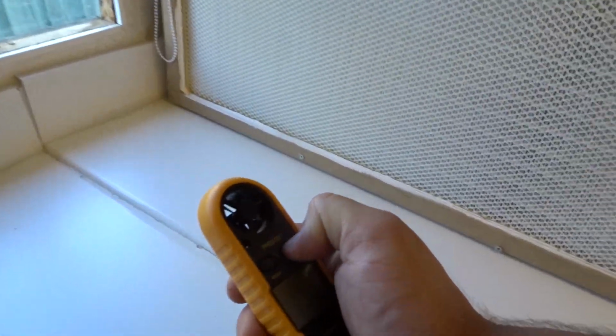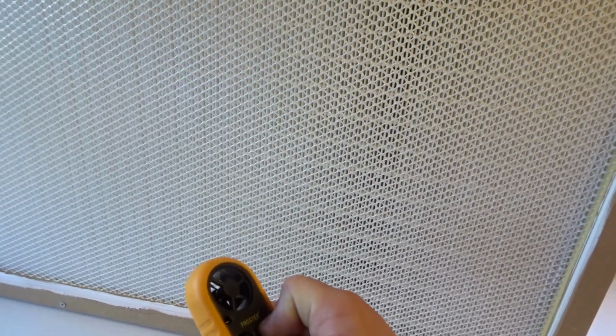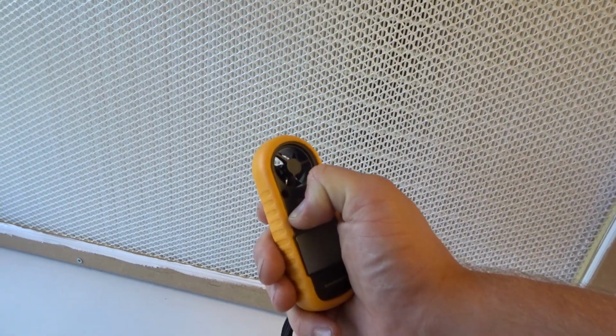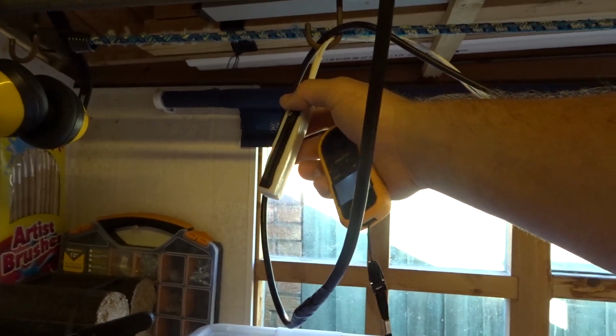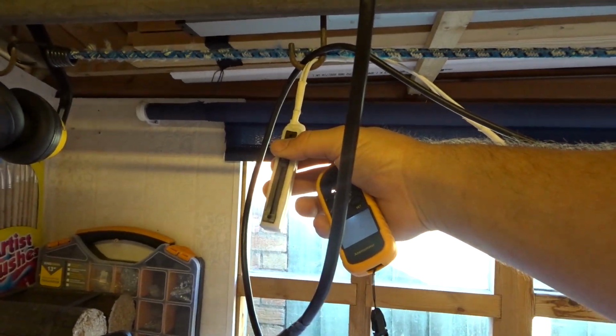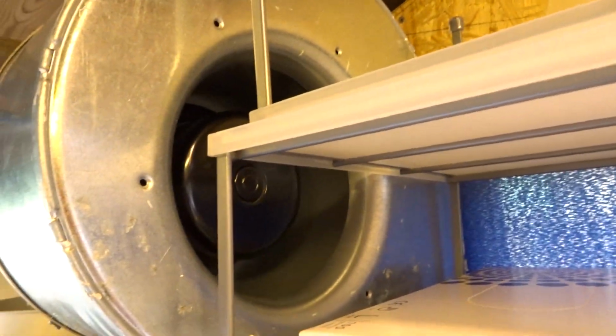Let me just fire it up and I'll give you a quick demo of what it does. There is not a consistent blow across the HEPA itself. So what we've got to do to overcome the initial inertia is fire it up to like 10% or whatever, and then we can fire it all the way up.